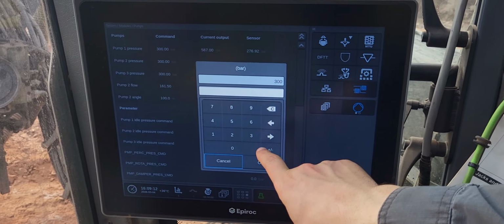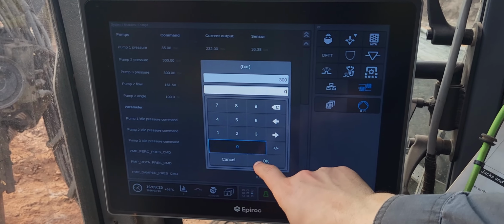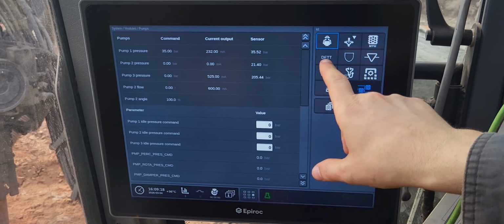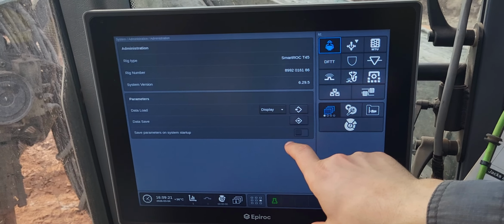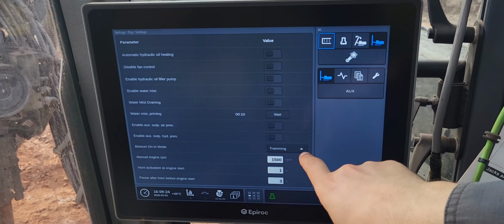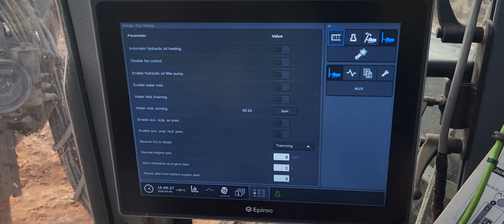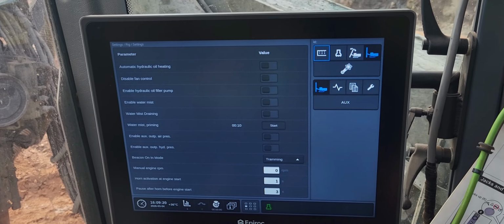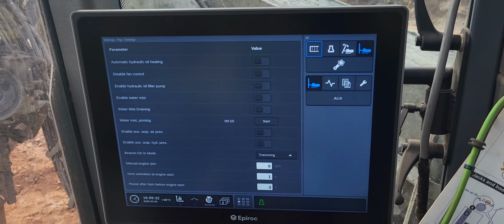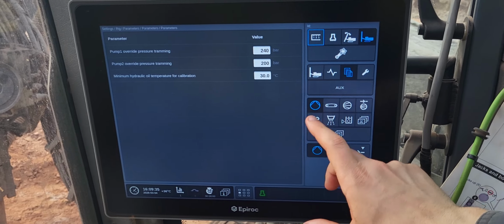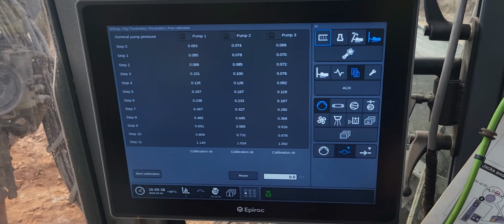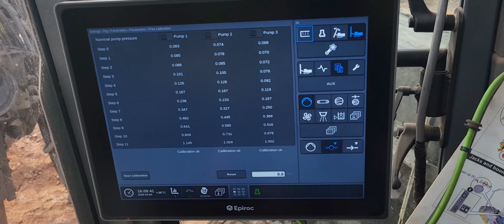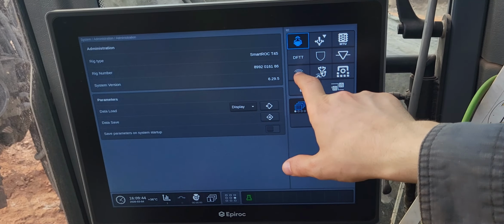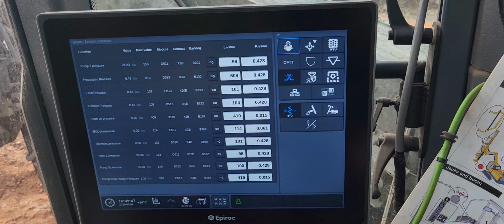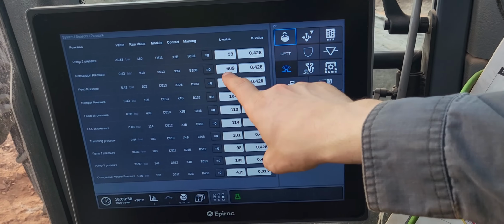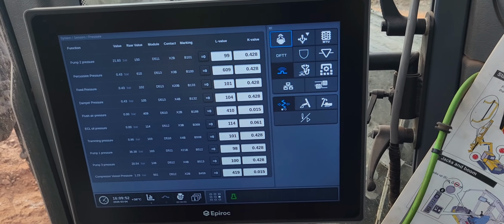After that we need to always go to zero. And then we go to zero as well on the RPMs. It's very important to not forget. That's it. So on this machine we know that 100% the pumps and the sensors of the pumps are perfect. The thing that is broken here that we have to replace is the percussion pressure sensor. Yeah, because the L value is too high, out of the standards.